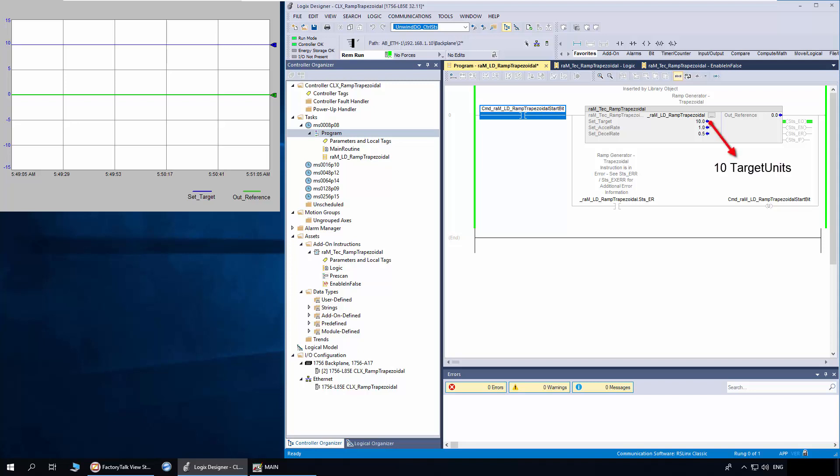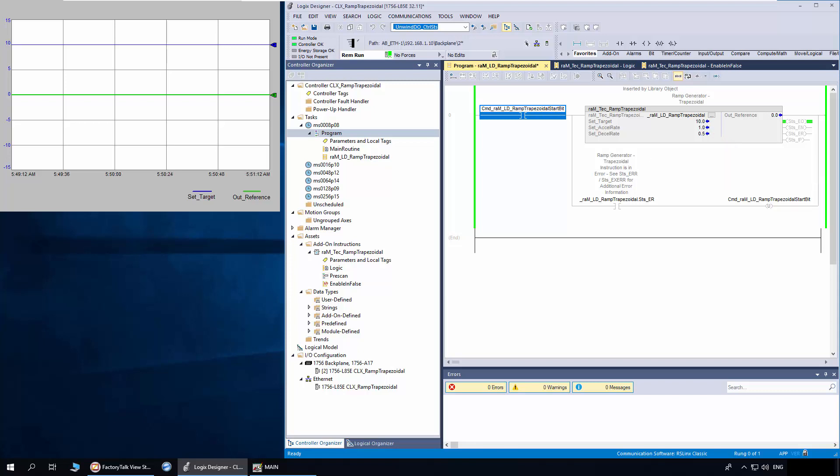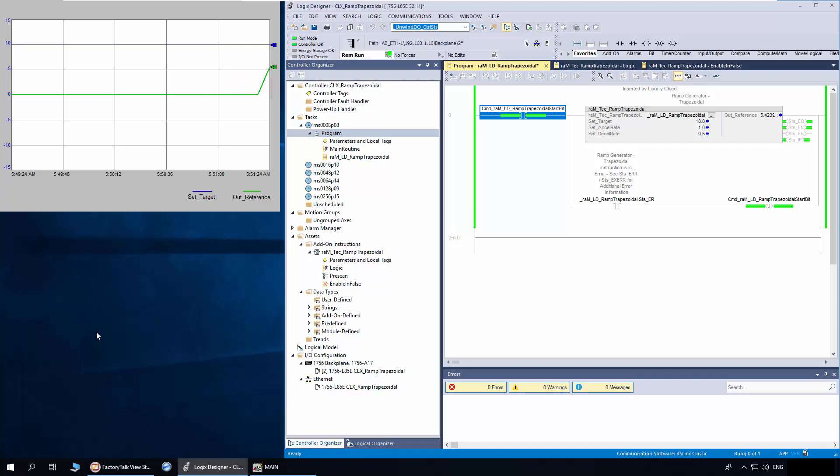I have set the target as 10, set accelerate as 1 and decelerate as 0.5. I will toggle the start bit and make the rung condition true. You can see in the trend the out reference is ramping at the rate of accelerate. Now the out reference has reached the set target.